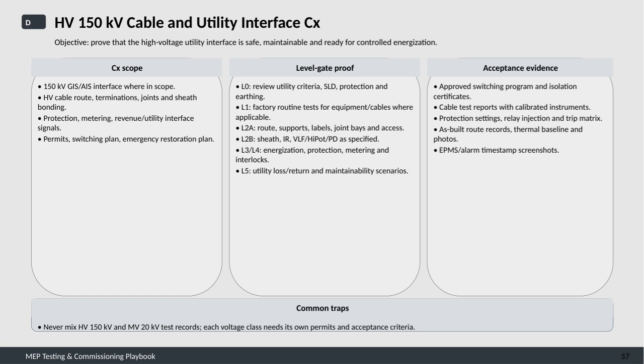Level 2A focuses on the physical installation, including route supports, labeling, and joint bays. Level 2B covers electrical tests, such as sheath testing, insulation resistance, very low frequency, high potential, and partial discharge tests as specified.